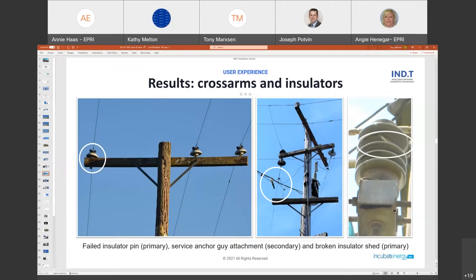This defect was actually more than 1,000 feet off, on a tap line from the monitored power line, but it showed up at the point where the tap line joined the power line. When we walked the tap line, sure enough, there it was. You can't really see it in this photo, but the skirt under the insulator was pretty filled with dirt because it had sat down and rolled over, and the creepage path length had been greatly shortened by this failure of the peg.